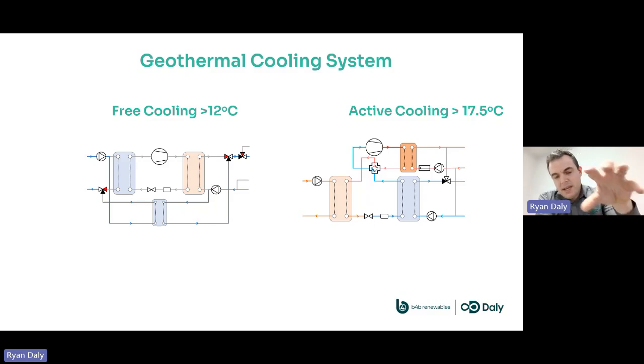And at the same time, that heat that's in your building will be put back into the ground. And then the benefit of that is that you're coming in at a higher temperature than in the winter months when you start to take heat out of the ground again. Active cooling is actually then running the compressor to chill that water down to a lower temperature. And then in our case, in our own house, we have that set to 18 degrees.